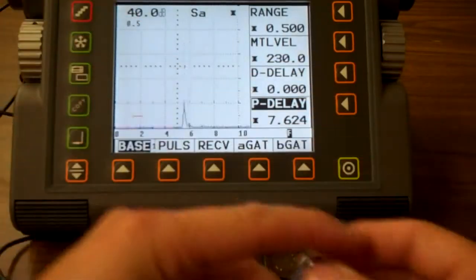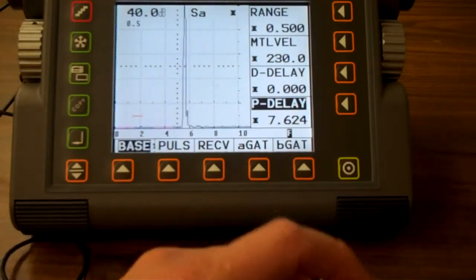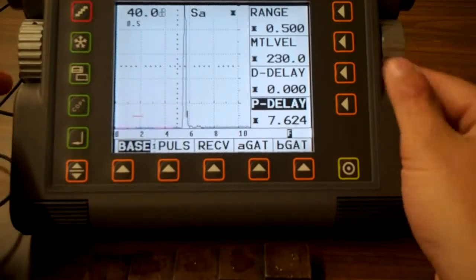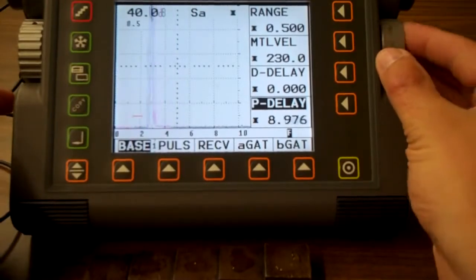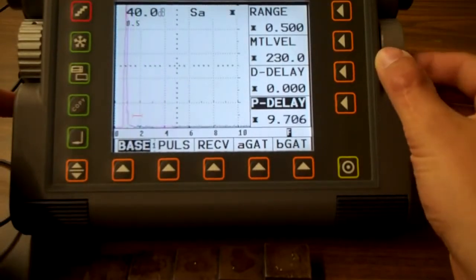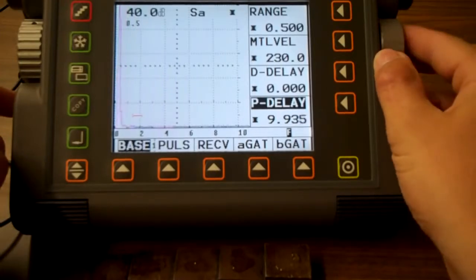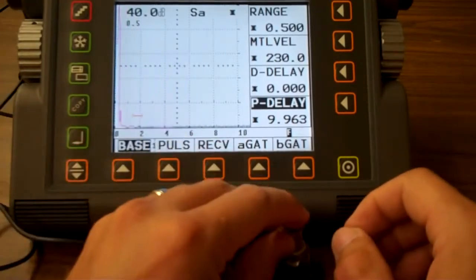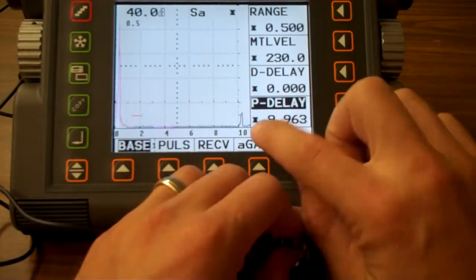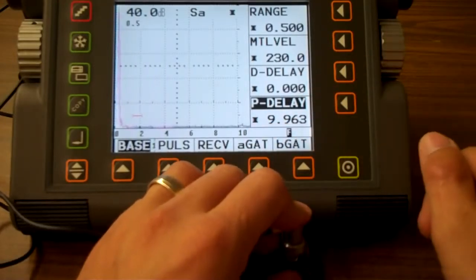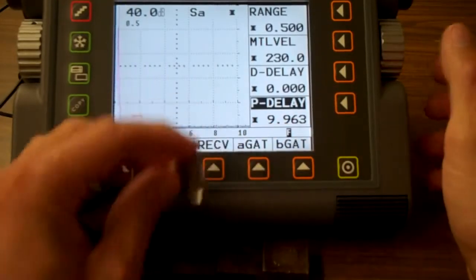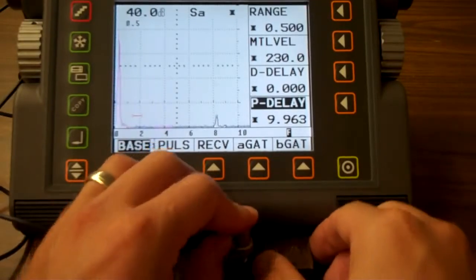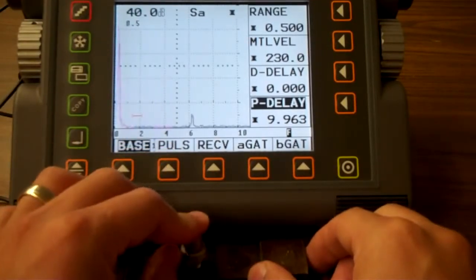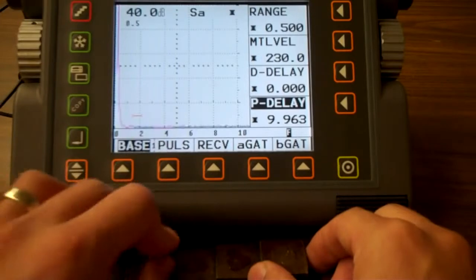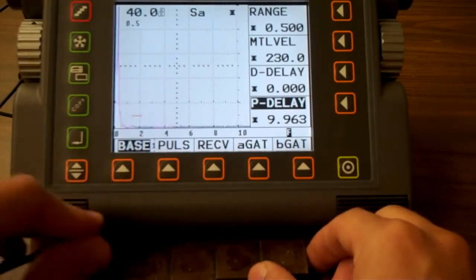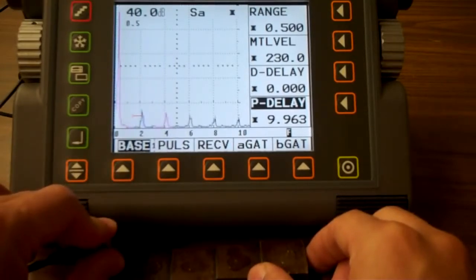Alright, that looks good. I wiped the couplant off. So that's a pretty clean looking signal. So I'm going to push that guy over and make him my initial pulse now. So probe delay, that thing over. There we go. I've still got my gate. That brings my 0.5 signal in pretty quickly, right there at 100%. Just for kicks and grins, let's see where it lands. 80%, 60%, 40%, pretty close, and 20, 40, 60, 80, 100.